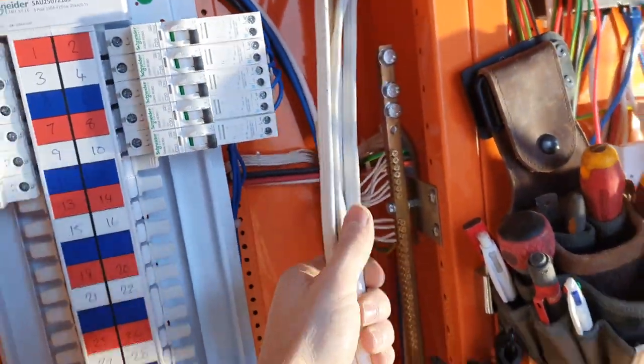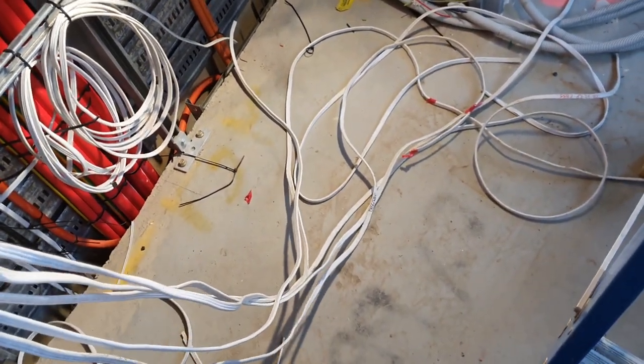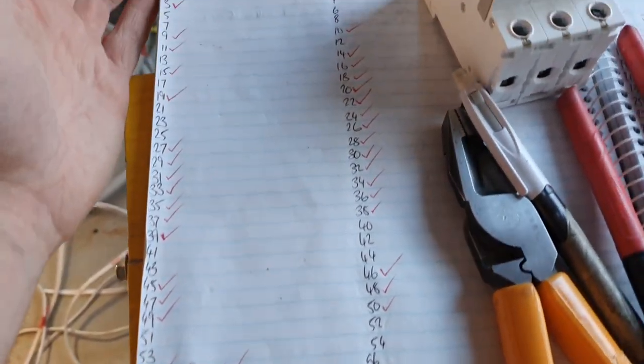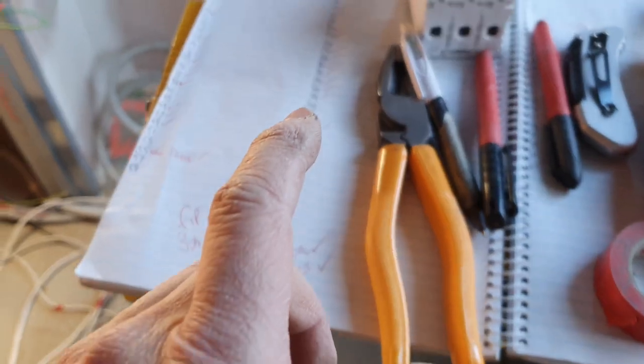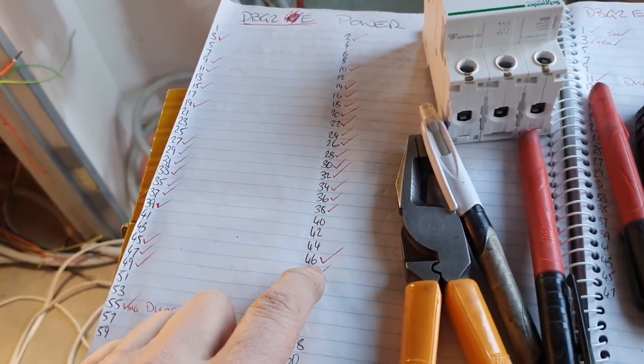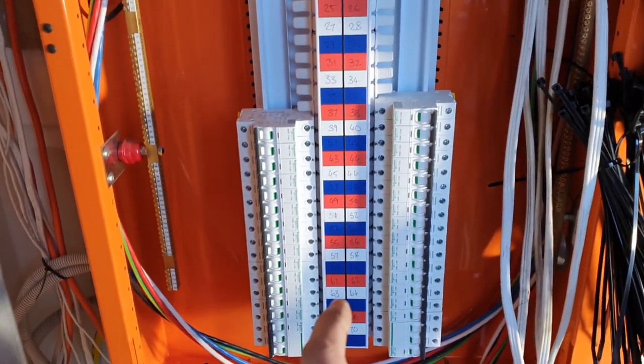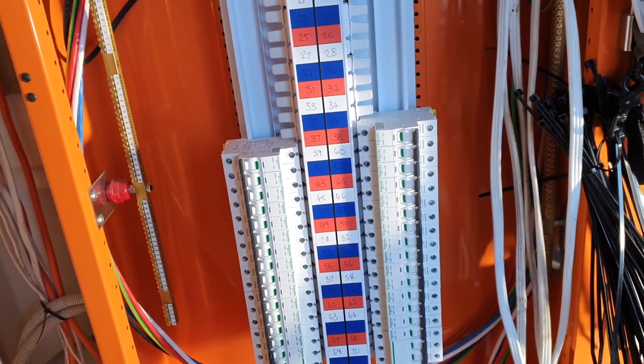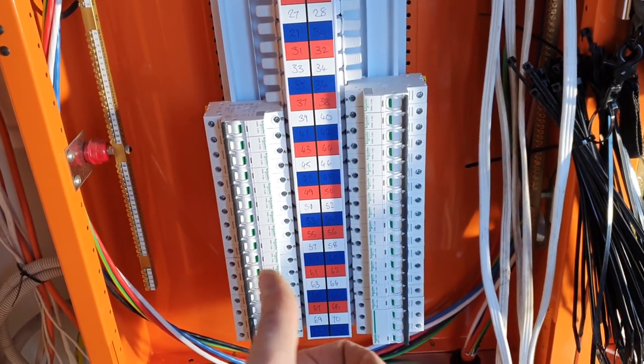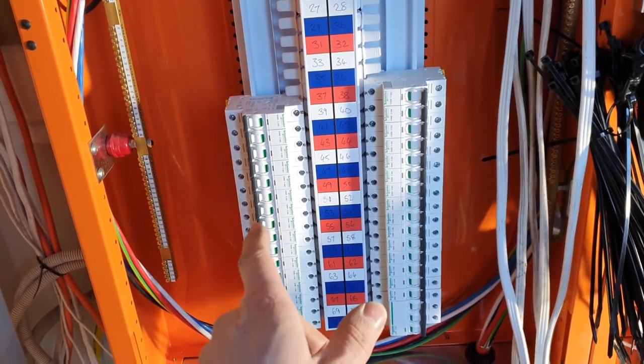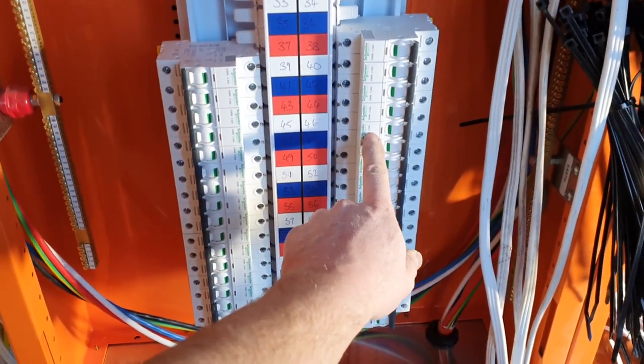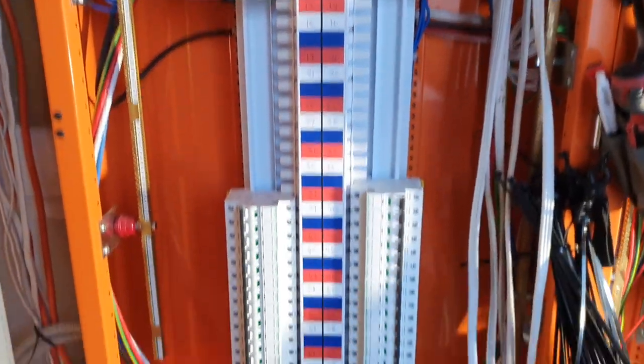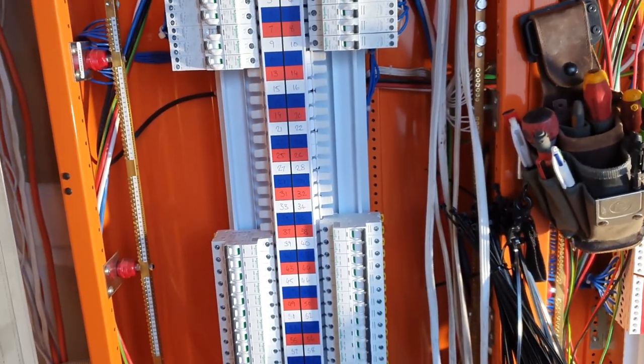So I've got a few circuits left here. These ones have been added on the job and I haven't allocated them to a breaker here yet. So I've got my schedule here, I've ticked off all the circuits that I've got. So I need to double check this with the plan over here. This is a job for Monday, but I've got to double check this, make sure that 46, make sure where that goes. And then with this board in particular, this is the power essential board. So a lot of the medical service panels and panels that have rooms that have like an RCD in the room, resettable in the room, I have to run them off circuit breakers. So I need to double check that 46 is an RCD in the field sort of thing, and I don't have to swap this to an RCD here. So there's some RCDs up the top.